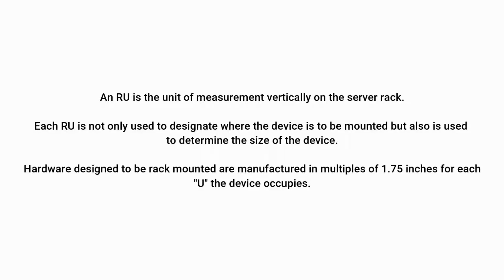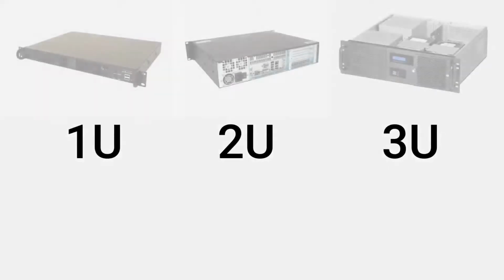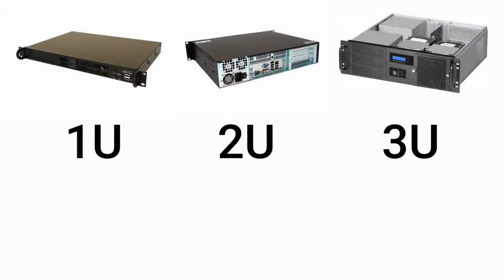Hardware designed to be rack-mounted are manufactured in multiples of 1 3/4 inches for each U the device occupies. A 1U device would occupy a single RU. 2U devices occupy 2. 3U devices will occupy 3 RUs. And so on.